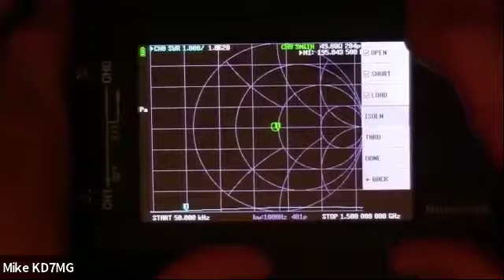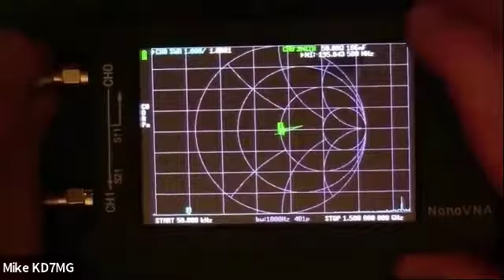We have 5 different places to save this. I'm going to save in 0. Now with 0, that is the default when you turn the unit on. It will always go to 0. It will remember your setup. It will remember the calibration. A full sweep calibration is always best done stored in 0. We may not have to do any more calibrations.